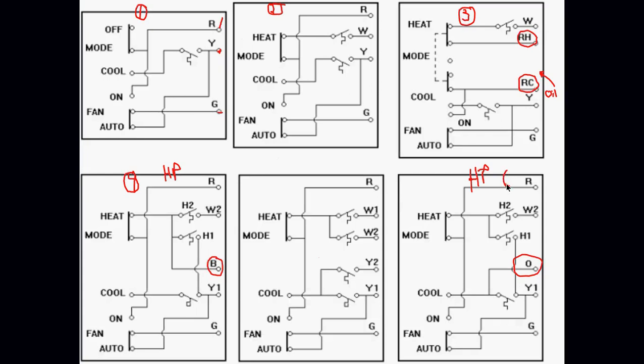Okay, and again, I don't want to get too far ahead of myself because I haven't even really talked about what a heat pump does yet. Okay, so 4 and 6 are essentially the same, just one's older style? Yeah, 4 and 6 are essentially the same thermostat, but we just energize the reversing valve on number 4 in heating mode, and in number 6, we energize it in cooling mode.